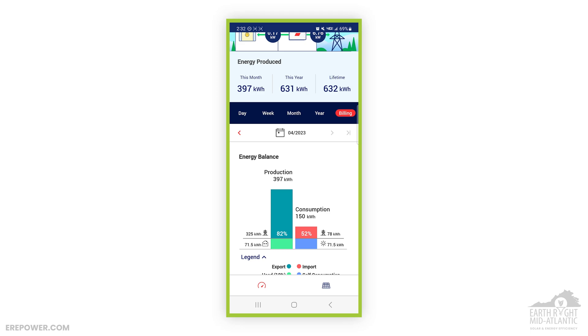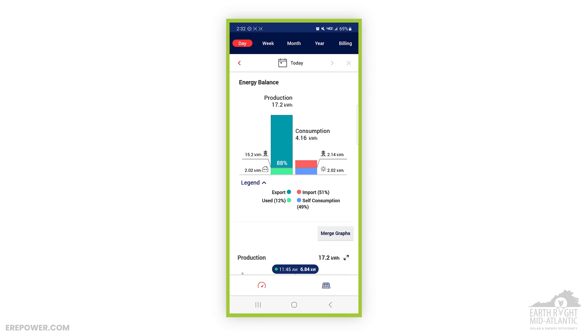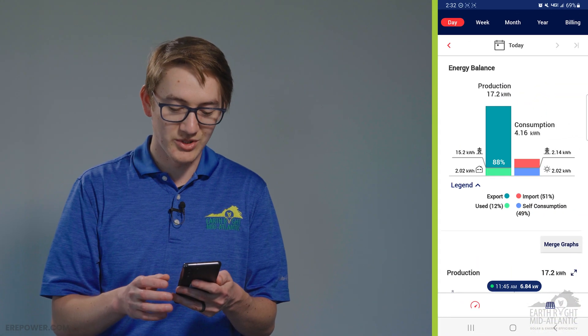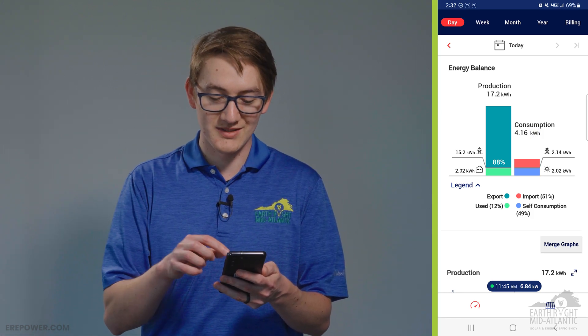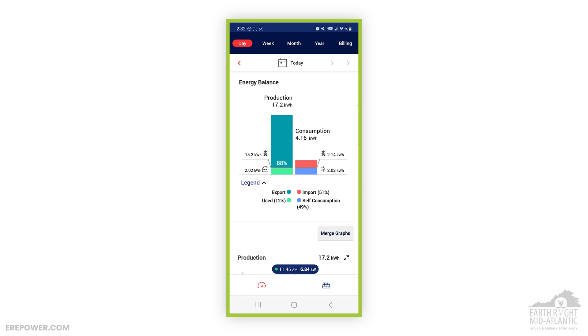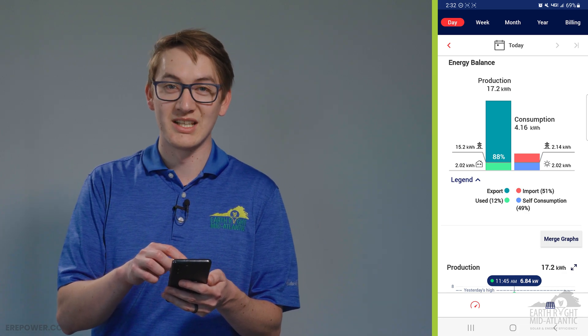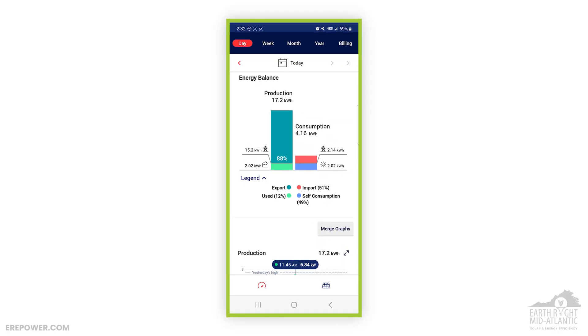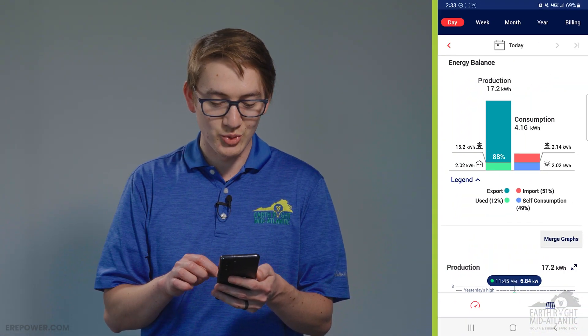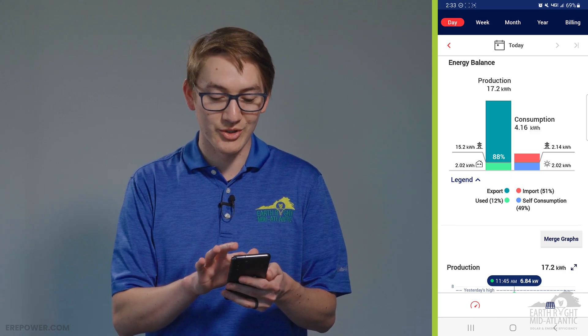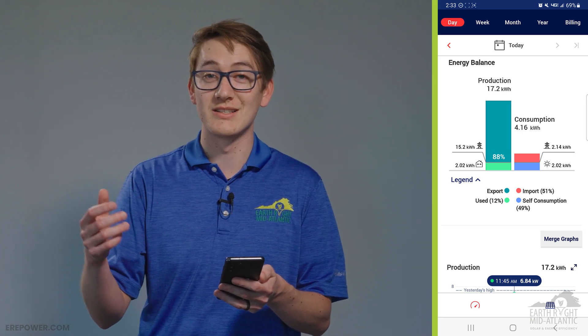This is what has been produced today. You have two columns: production and consumption. Production is what your system is making; consumption is what your home consumes. So far today this system has produced 17.2 kilowatt hours. Of that 17.2 kilowatt hours, 2.02 kilowatt hours have been self-consumed — that's power that went directly from your solar panels through your inverter to power your home. The self-consumption value on the production side always matches the self-consumption on the consumption side. In this instance, 15.2 kilowatt hours were sent back to the grid, so this homeowner has earned 15.2 kilowatt hours worth of credits for that day.